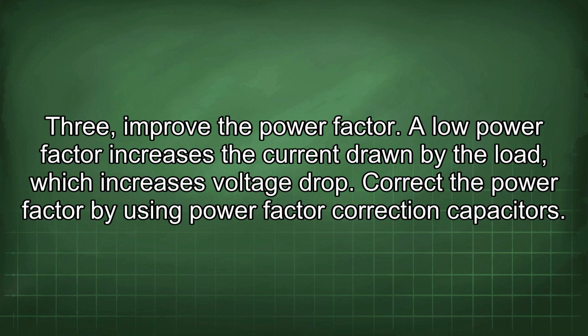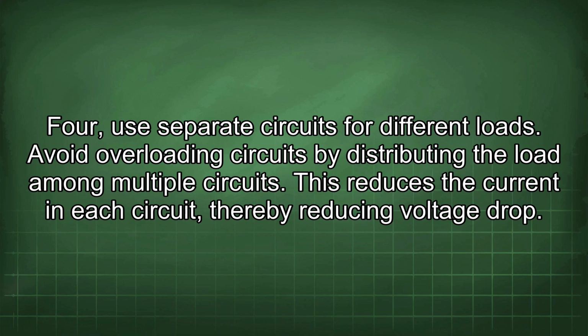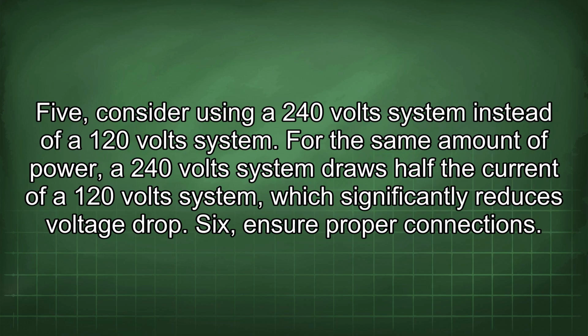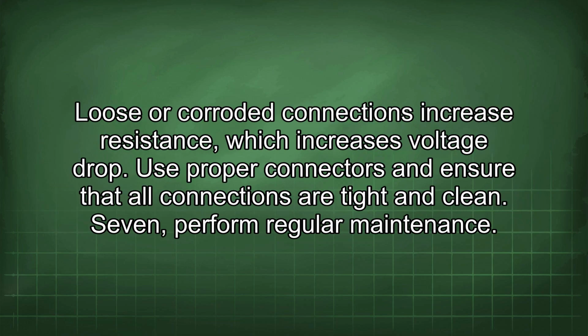3. Improve the power factor. A low power factor increases the current drawn by the load, which increases voltage drop. Correct the power factor by using power factor correction capacitors. 4. Use separate circuits for different loads. Avoid overloading circuits by distributing the load among multiple circuits. This reduces the current in each circuit, thereby reducing voltage drop. 5. Consider using a 240-volt system instead of a 120-volt system. For the same amount of power, a 240-volt system draws half the current of a 120-volt system, which significantly reduces voltage drop. 6. Ensure proper connections. Loose or corroded connections increase resistance, which increases voltage drop.